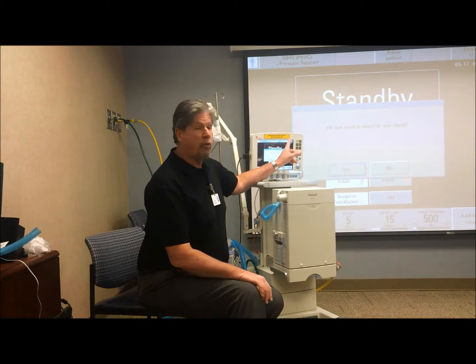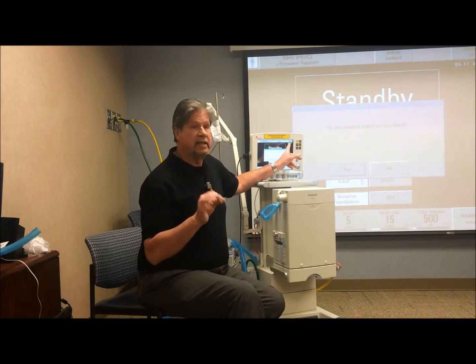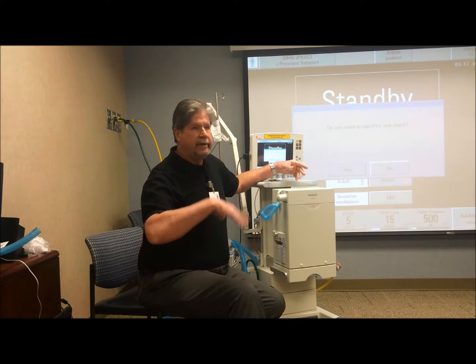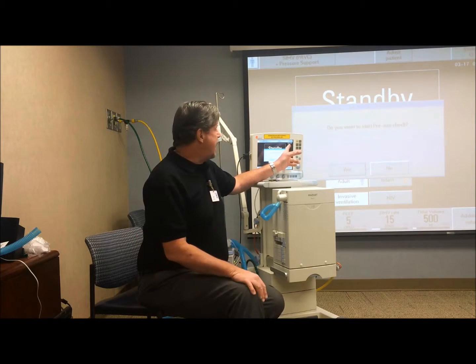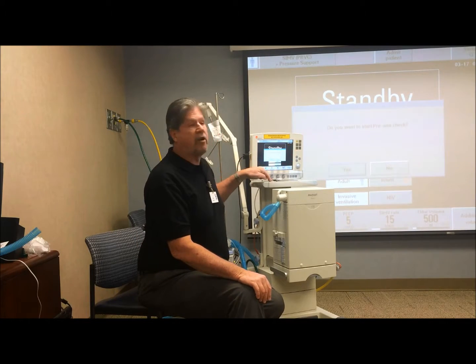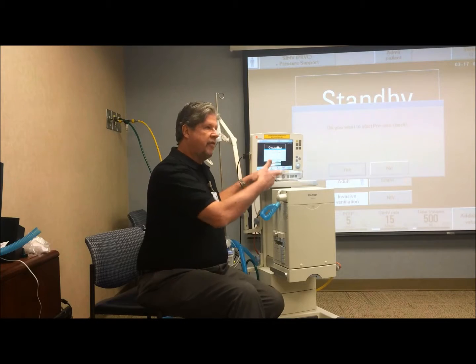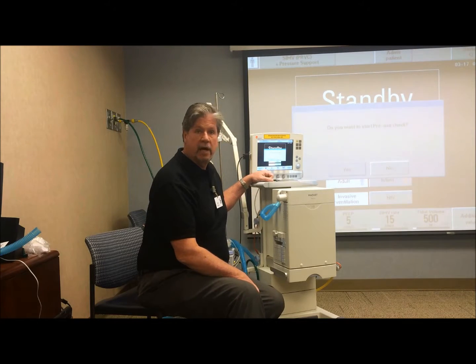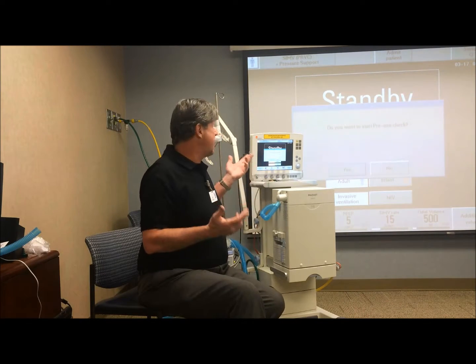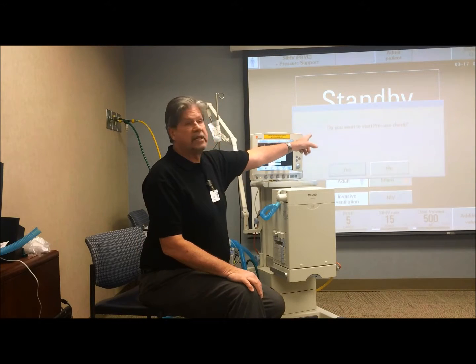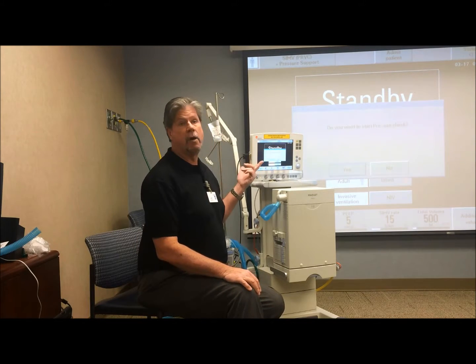There's an electronic record in the ventilator that says that the pre-use check was done on February 15th, and there might also be a sticker on it that you would put on the ventilator saying that the check has been done, on certain dates. So you go, okay, I'm just going to turn it on, and when you get this message, you just simply say no.